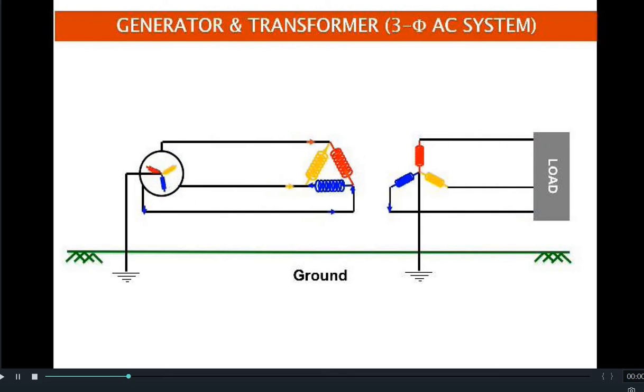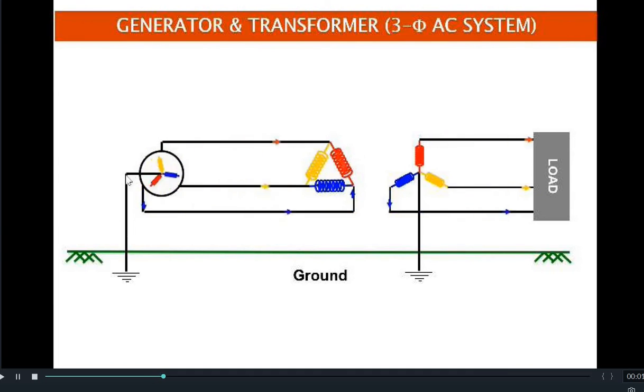In a three-phase AC system, a generator is connected to a transformer through transmission lines and then fed to the load. The systems we see around us are grounded systems — the neutrals of the transformer as well as the generators are connected to the ground. We impose the neutral potential of zero volts onto the ground, so whenever there is a fault in any phase, the fault current flows towards ground and back to its source through the shortest path.